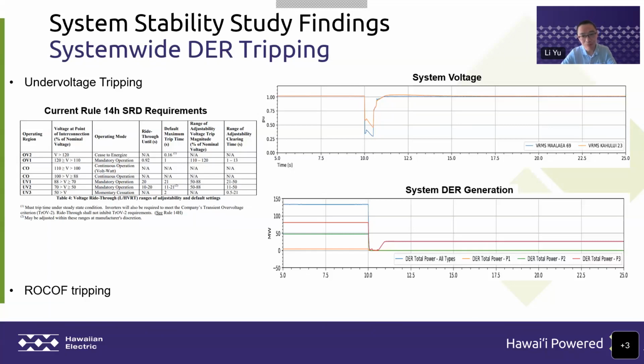Another thing is that we frequently see many scenarios in our planning event simulations where the system frequency change can be very fast. I think that's reasonable when we have very low physical inertia and a lot of DER. The rate of change of frequency in the simulation, over the 0.1 second time frame, can range from 1 hertz per second to 6 hertz per second. So that basically means the current IEEE 1547-2018 Category 3 DER rate-of-change-of-frequency ride-through requirement, which is 3 hertz per second, may not be good enough for us.